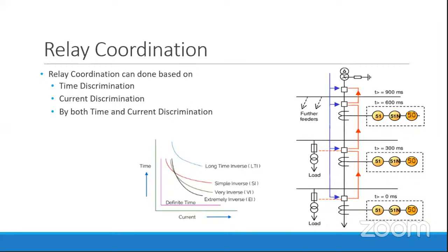50 and 51. 50 means AC instantaneous overcurrent, and 51 is AC time overcurrent, also used for earth fault protection. So 50 will be the primary protection and 51 will be the backup protection. Likewise for these feeders and for the downstream feeder. In time discrimination, we should give a time margin in such a way that if any fault occurs at this feeder, for this network, the fault should be cleared instantaneously, in a definite time. That is, we can say 0 milliseconds. The fault should be isolated in 0 milliseconds.